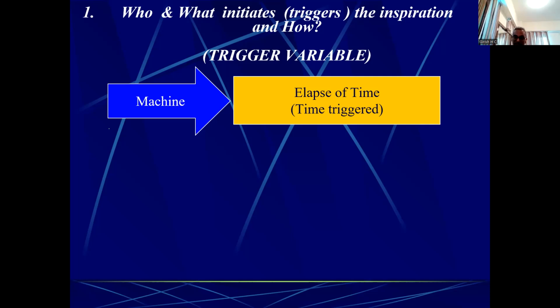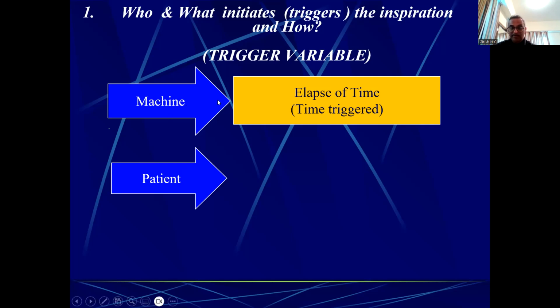No matter what, every 3 seconds, machine will give a breath. What you are talking about, pressure and cycle triggering, we will come to that. See here in the machine, the clinician is telling the machine to give a breath. That means I have set a rate of 20. That means I'm telling the machine, give a breath every 3 seconds. That's it. The machine will do that. Now, if I want the patient to determine when to breathe, then how does the machine know? How does the patient tell the machine when to breathe?